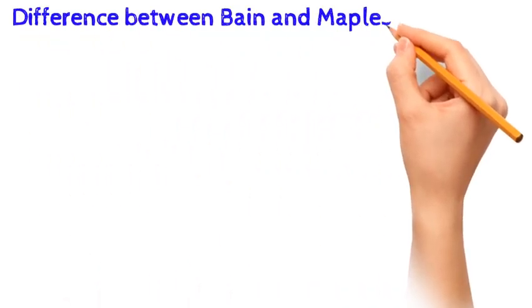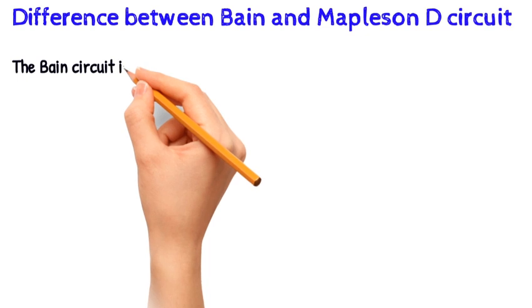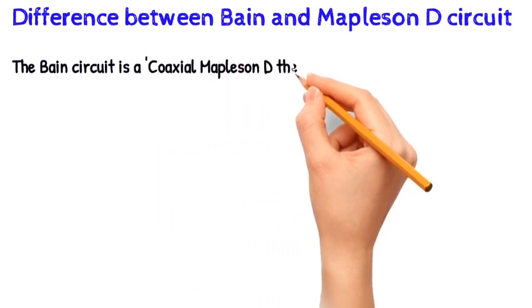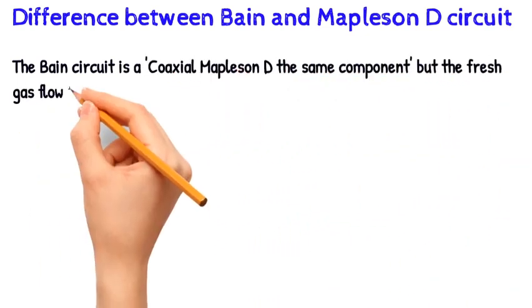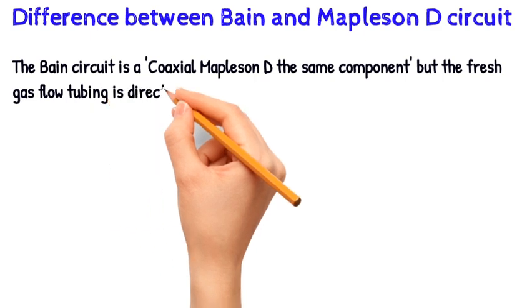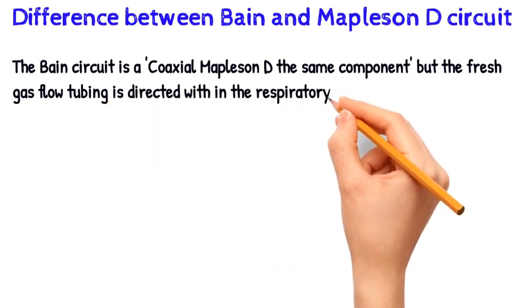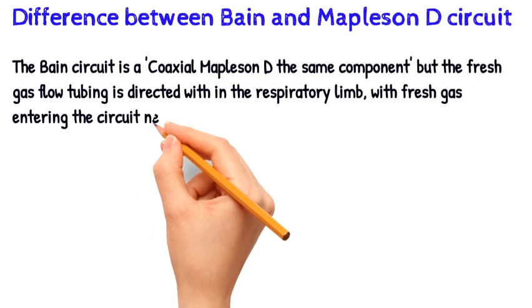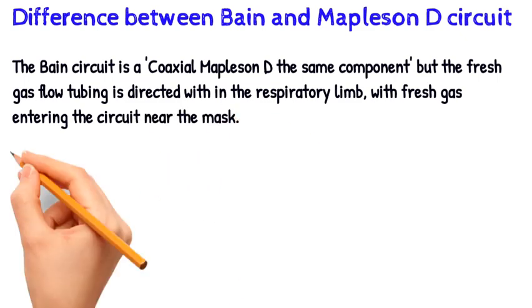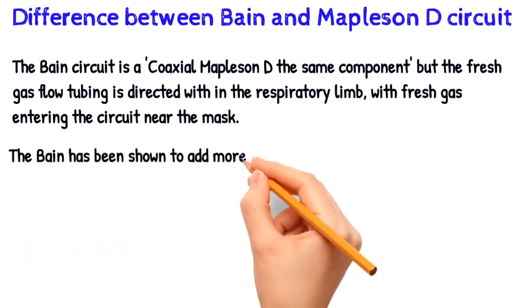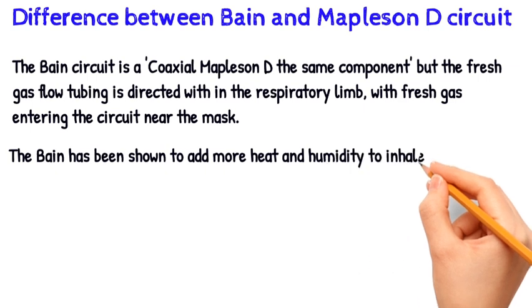The difference between the Bain and Mapleson D circuit: the Bain circuit is coaxial, while the Mapleson D has the same components but the fresh gas flow tubing is directed within the respiratory limb, with fresh gas entering the circuit near the mask. The Bain circuit has been shown to add more heat and humidity to inhaled gases than other Mapleson circuits.